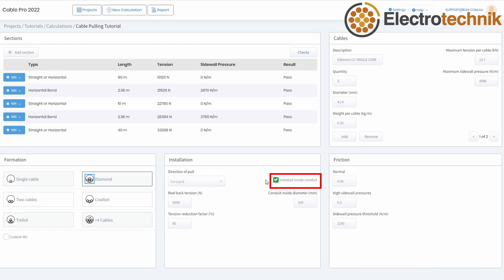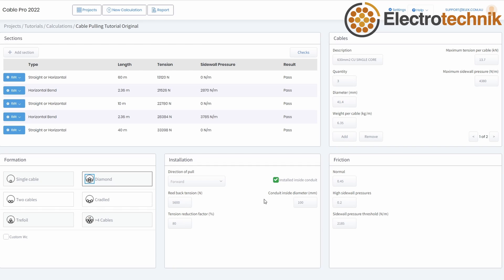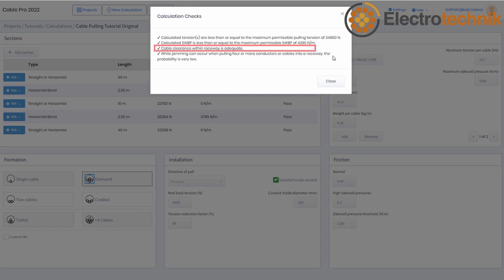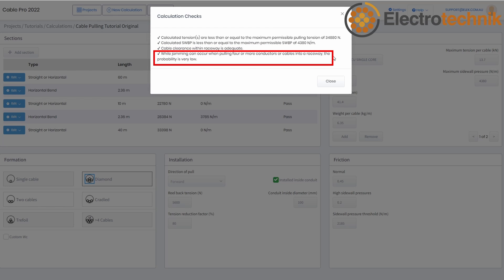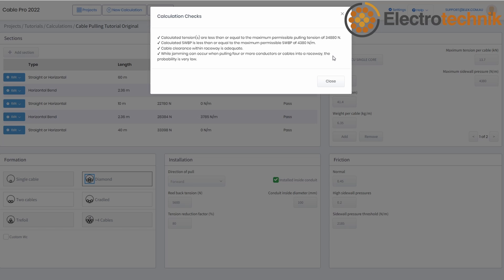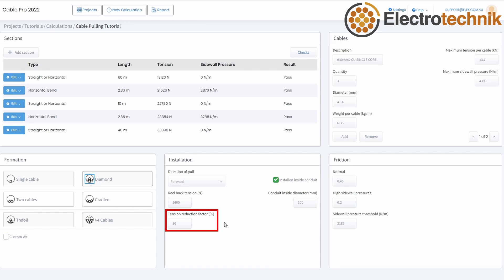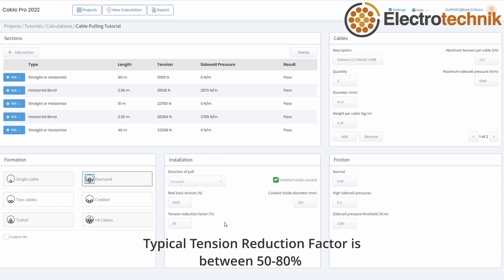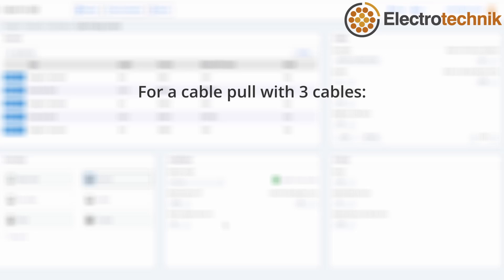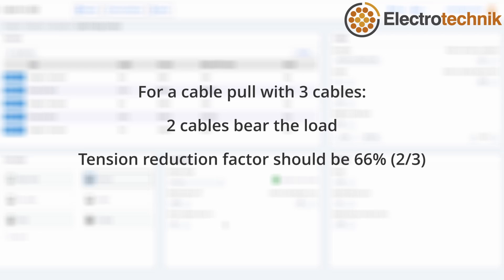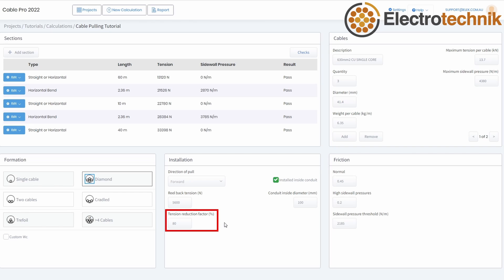The installed in conduit selection should be checked for cables being pulled inside conduits, or unchecked for cables being pulled along a cable ladder. For cables installed inside conduits, you must enter the conduit inside diameter, and certain checks will be made, such as a cable clearance check. The probability of cable jamming is also checked, and a warning will appear if there is an issue. The tension reduction factor is typically used for multiple cables where the forces are not evenly distributed among each cable — typically this value will be between 50 and 80%. For example, if three cables are being pulled, it's recommended that two cables bear the load, meaning the tension reduction factor should be 66%. The default value of 80% is conservative and doesn't need to be changed.